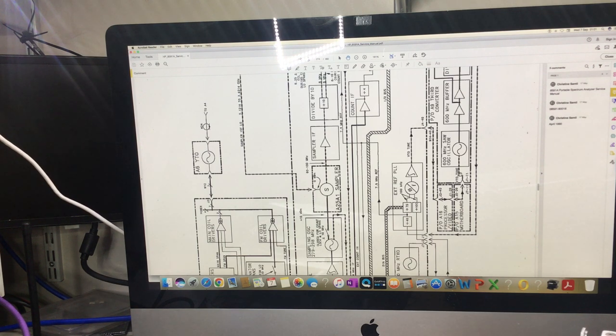If this is steering all over the place, and this isn't following it, then naturally that would indicate that the 600 MHz oscillator can't be controlled, so the fault's likely to be in the third converter. However, if this voltage does not change when we remove the 10 MHz reference oscillator signal, then the fault would be on the external ref PLL board, which I think is on the A25 module on the frequency counter. So I think that's where we're going to have the issue, if that's the case. But it's just a case now of going on to J1 pin 11 of the motherboard, where the third converter connects, to see what the VTO tune line's doing.